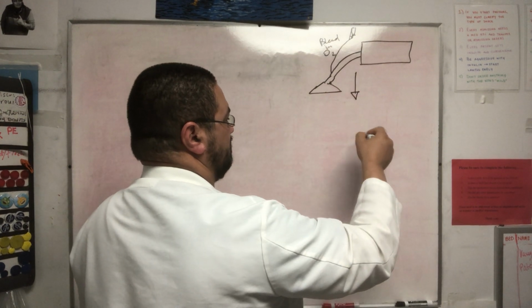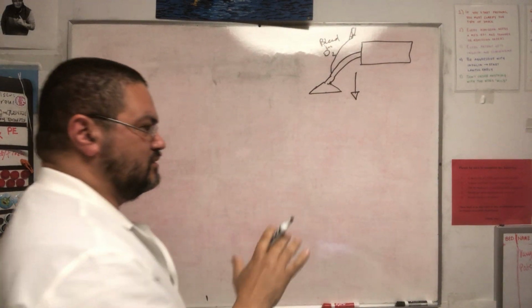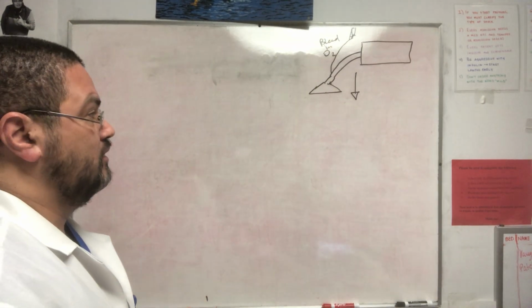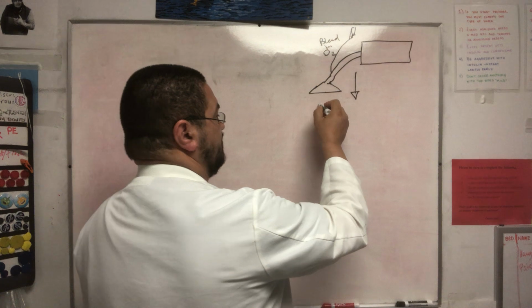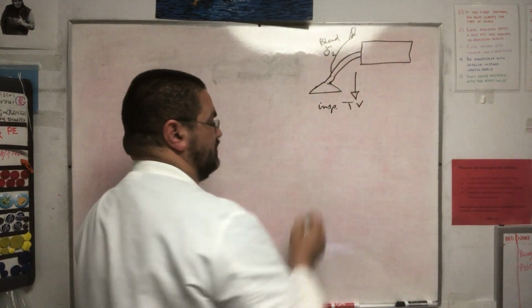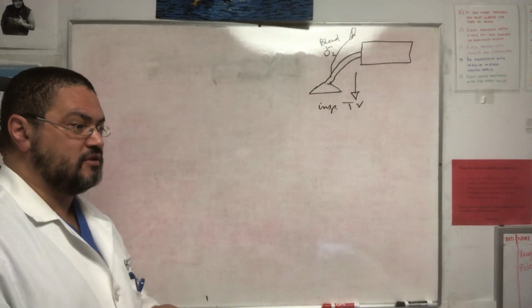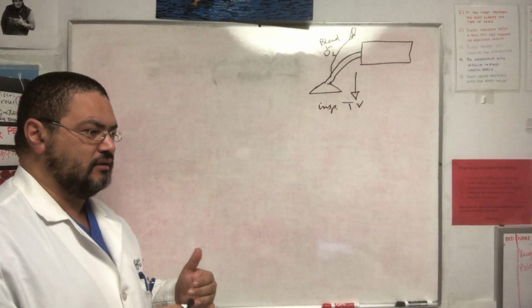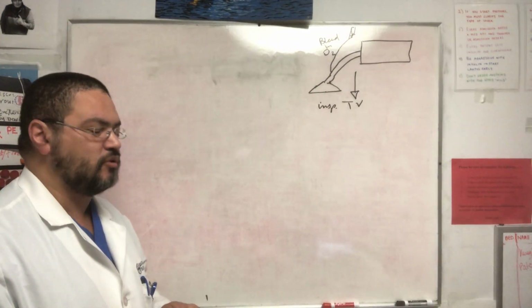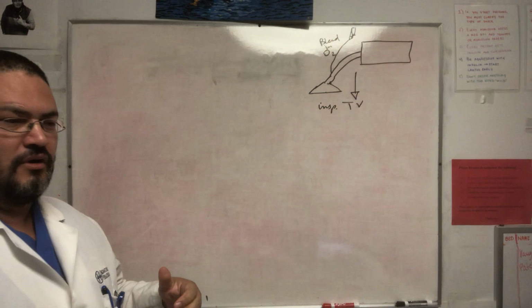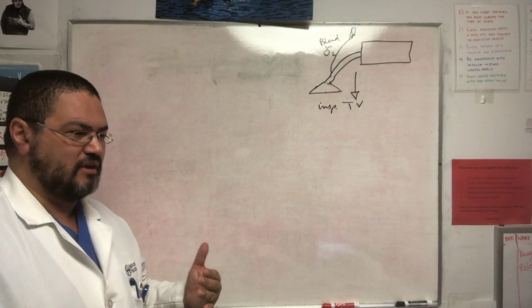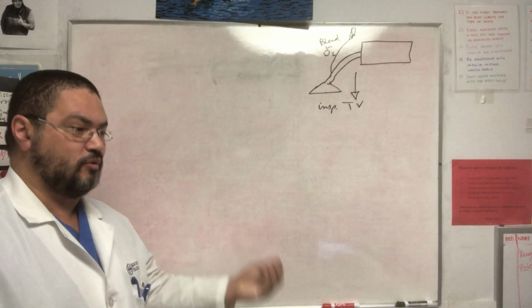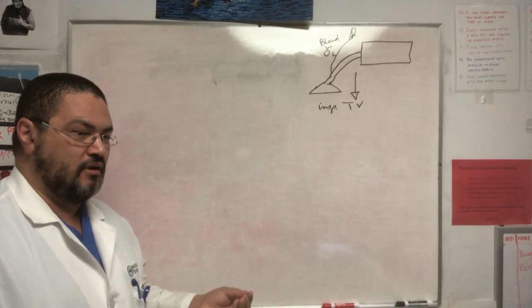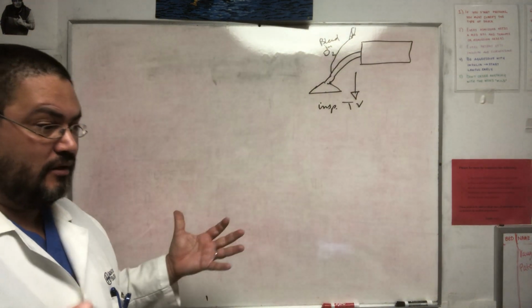Now the BiPAP after that started to get better, and we started seeing BiPAPs where you can titrate the oxygen, and you can somehow see what's going on with the patient. You can see the tidal volume, for example, that the patient is getting. Traditionally, BiPAP, by the way, gives you inspiratory tidal volume. So when the nurses or somebody come to you and say the tidal volume is low on the vent, guaranteed 100% of the time, what they mean is the expiratory tidal volume. But if somebody says the tidal volume on the BiPAP is low or high or whatever, they mean the inspiratory tidal volume. And that sometimes freaks people out, because they say the tidal volume is 1200 cc's.